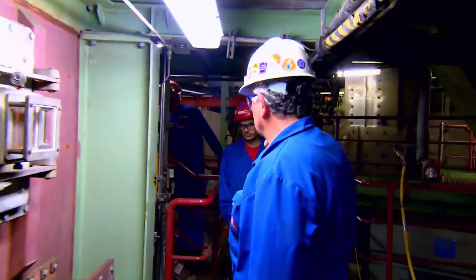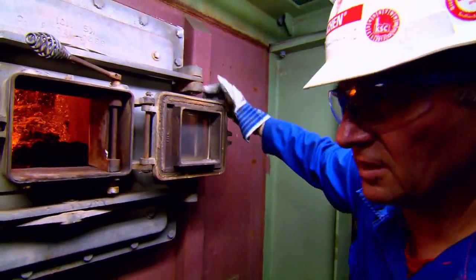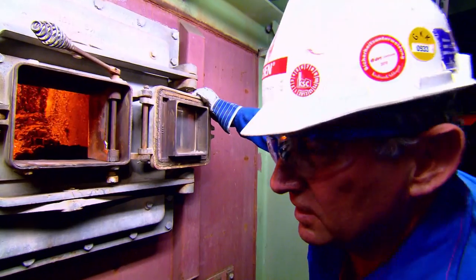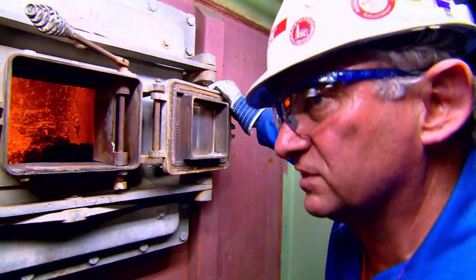Frank Holm Novotnik and his team now really have to go for it. Not a nice place to work — hot, dangerous and unbearably loud. Our customer has commissioned us to blast away the slag in the upper grate area. The issue is that this lump weighs about two and a half to three tons. If this monstrosity blocks the shaft, part of the power station will have to be shut down. We can prevent this by setting up a very special explosive charge for this lump — and that's what we're going to do.